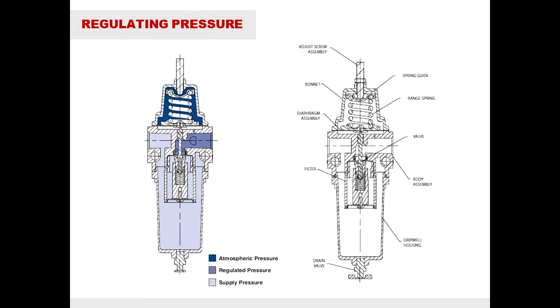If the regulated pressure becomes too high, an upward force on the diaphragm occurs. This upward force, in turn, closes the valve, allowing the pressure to lower back down to equilibrium.